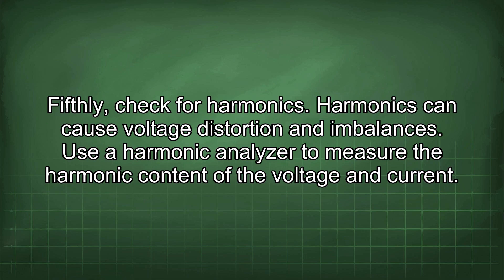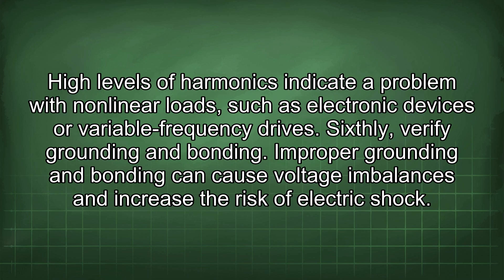Fifth, check for harmonics. Harmonics can cause voltage distortion and imbalances. Use a harmonic analyzer to measure the harmonic content of the voltage and current. High levels of harmonics indicate a problem with nonlinear loads, such as electronic devices or variable frequency drives.